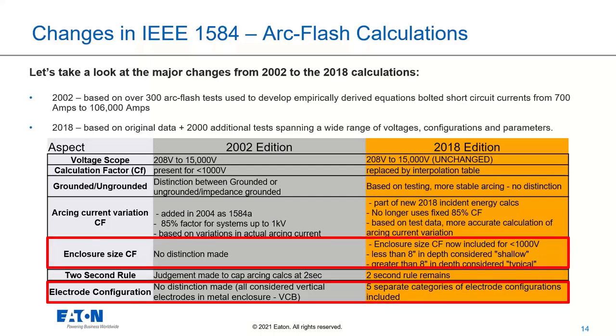There's a few other nuances in the changing, a little bit of, again, more semantics, but the biggest two that we're looking at in these new findings is they did these additional 2,000 tests on these different ranges of voltages and these electrode configurations. What we found was that essentially the enclosure size, the physical size at which the three-phase bus work sits in, that makes a huge difference.